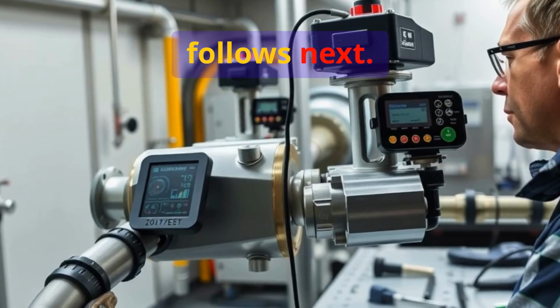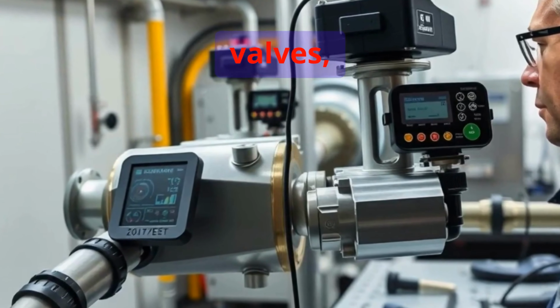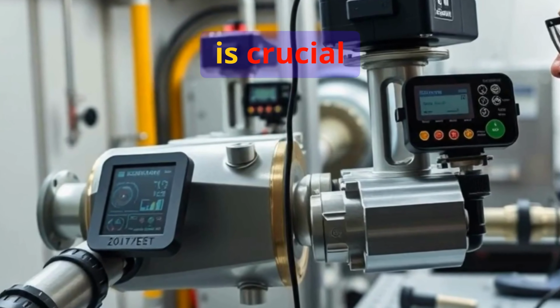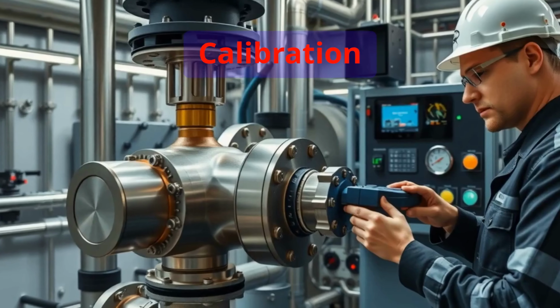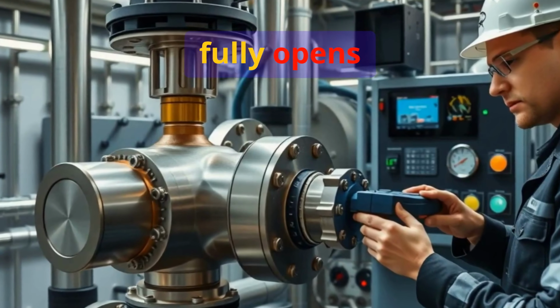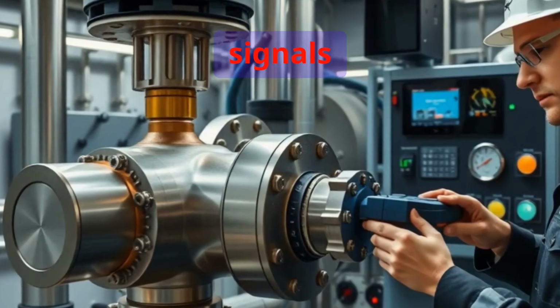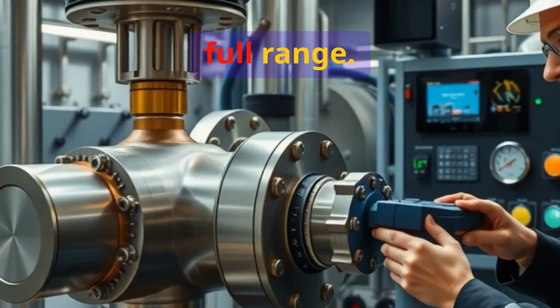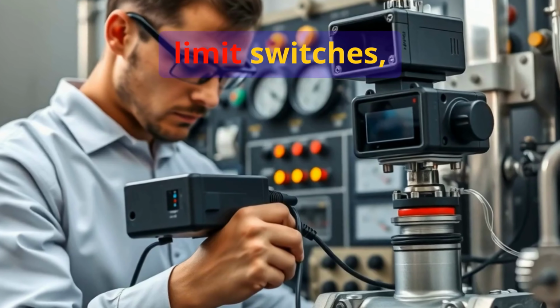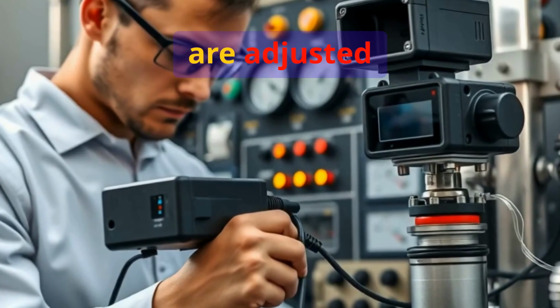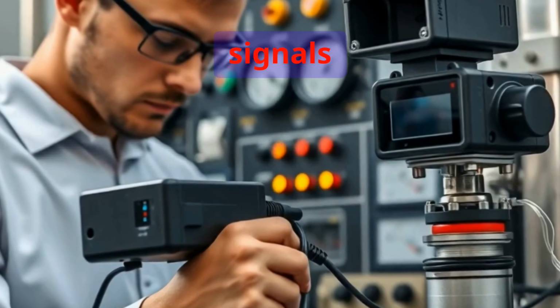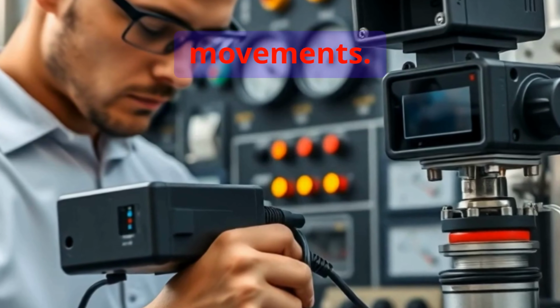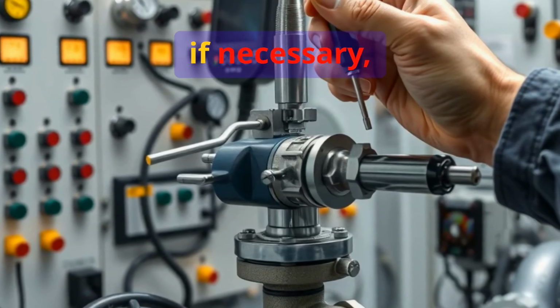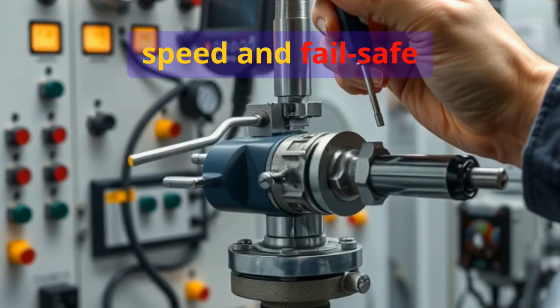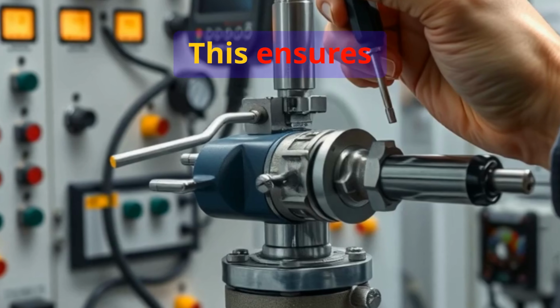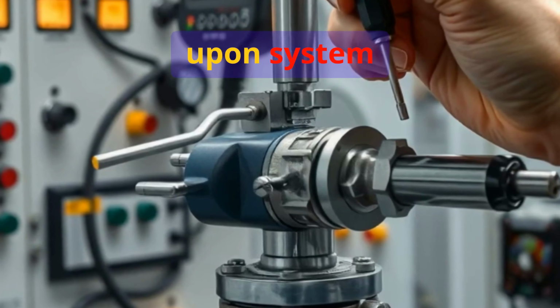Initial calibration follows next. For control valves and actuated valves, precise response to input signals is crucial for process reliability. Calibration procedures confirm that the valve fully opens and closes in response to designated control signals, and that it modulates accurately across its full range. Positioners, limit switches, and feedback devices are adjusted so that electronic or pneumatic signals correspond precisely to mechanical movements. Calibration data is recorded, and, if necessary, the actuation speed and fail-safe positions are fine-tuned. This ensures consistent, predictable control immediately upon system startup.